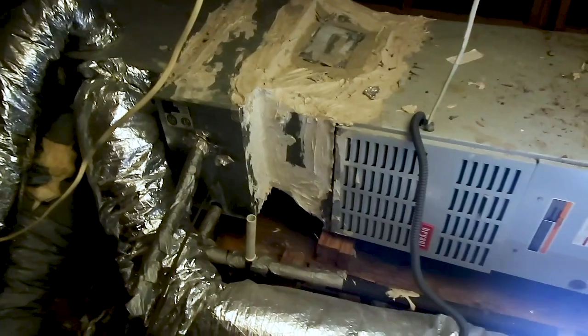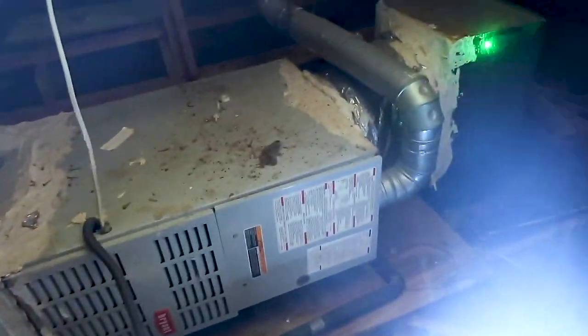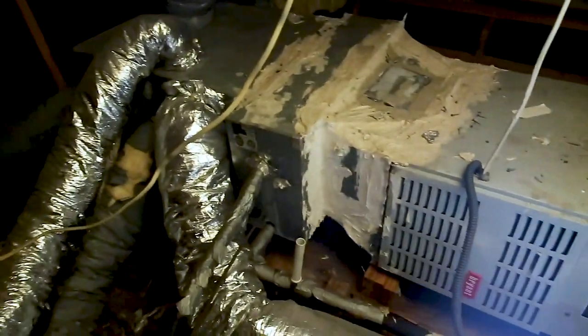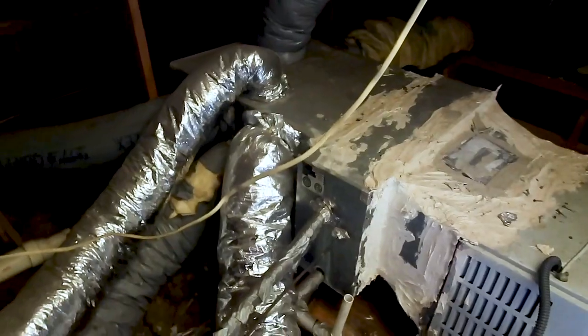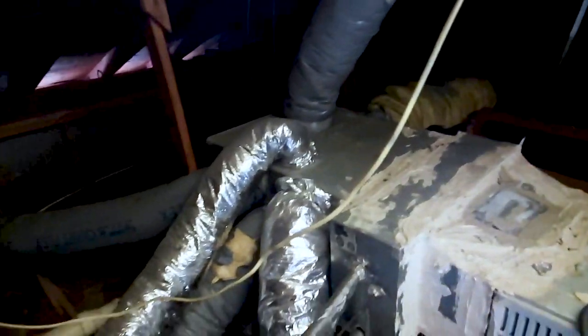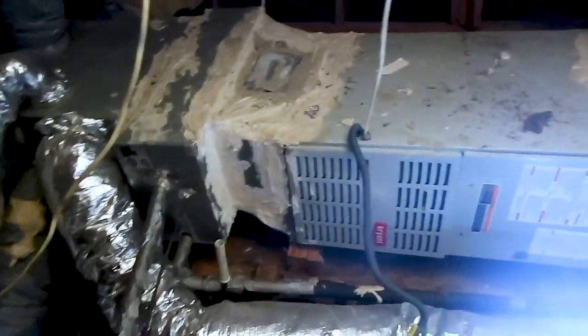After I broke down and called out everything I can on this HVAC system, I'll move on to the ductwork around the system. You can see that the ductwork is crimped. The gray ductwork is failing. It's not lifted and supported properly, and they didn't replace it all. You can even see the insulation breaking apart over that pipe too.